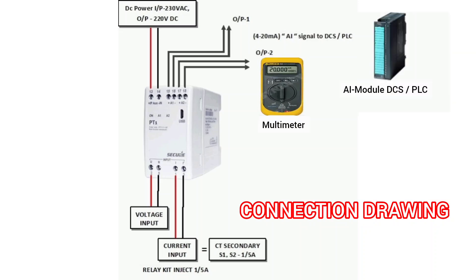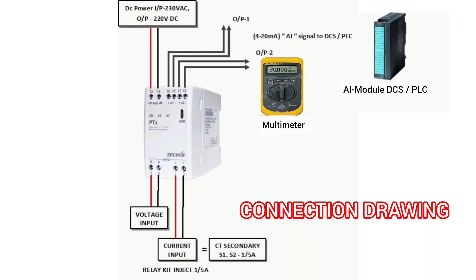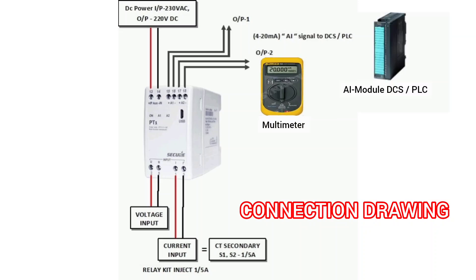We can connect both 4 to 20 milliamp output signals to DCS, PLC, or HMI systems to measure the load of the system. For switching the current transducer on or off, we have to give auxiliary supply of 220 volt DC or AC to terminals 13 and 14.